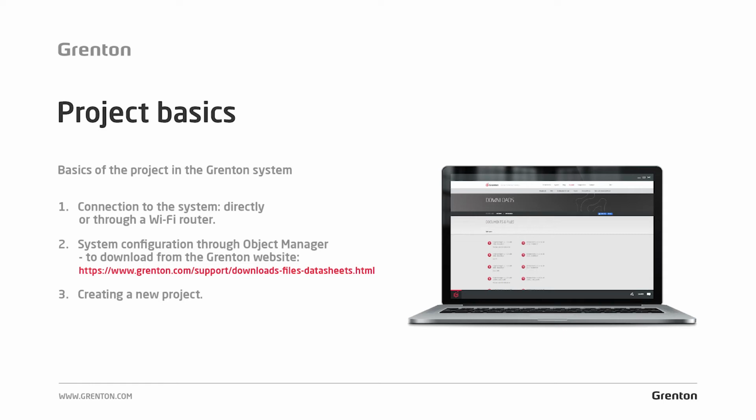Before you start creating the configuration, it is worth preparing the documentation for this system. So the order of work should be more or less like this. Connect the modules in the cabinet, all control modules. Connect the I/O modules to them. Then we make project documentation, i.e. we write that for the input in module 1, the first input, the switch in the living room, was connected, to input 2 the sensor from the corridor, to input 3 the switch from the kitchen. Of course, the serial number of this module should be noted as well.